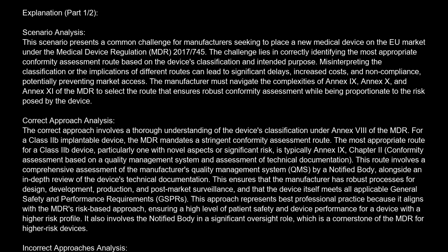Misinterpreting the classification or the implications of different routes can lead to significant delays, increased costs, and non-compliance, potentially preventing market access. The manufacturer must navigate the complexities of Annex IX, Annex X, and Annex XI of the MDR to select the route that ensures robust conformity assessment while being proportionate to the risk posed by the device.